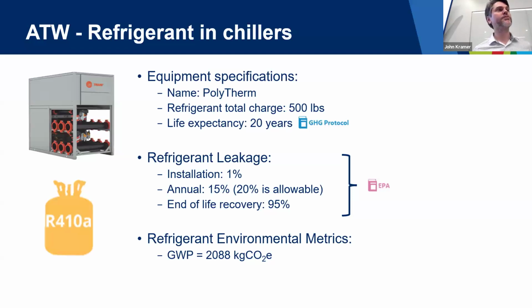I had to replace the refrigerant at my house twice in the last few years, and I have no idea why. So I had to fill it with 3 pounds of refrigerant. And from some of our commercial and industrial clients, we've heard the same thing: they'll have a leak, it's really hard to detect, so they just put more in. Instead of figuring out where the leak was, they just keep putting more refrigerant in. Not the ideal scenario. This refrigerant has a global warming potential of over 2,000 kilograms of CO2 equivalent. Not very good. I think they're currently replacing R410A with something like R32, which is quite a bit better, under 500, I think.